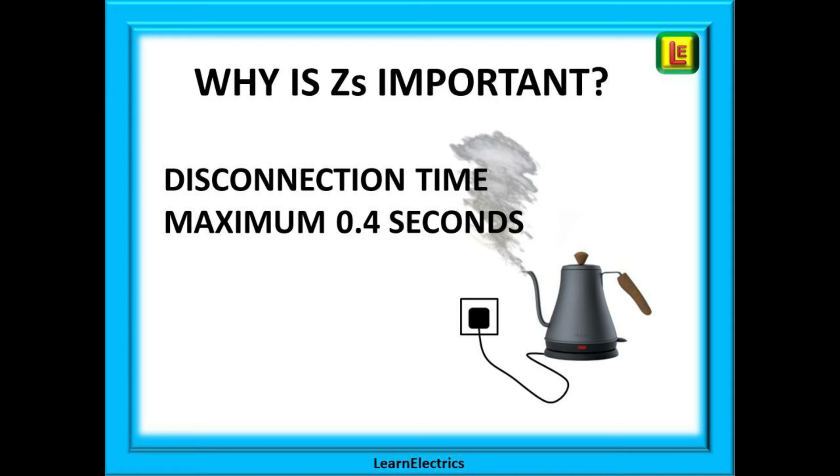The wiring regulations tell us that a fuse or breaker in a domestic final circuit such as sockets, lights, shower, etc., should disconnect the supply within 0.4 seconds, and to achieve this the ZS or impedance of that circuit must be below a certain number that is given in tables within the regulations book.